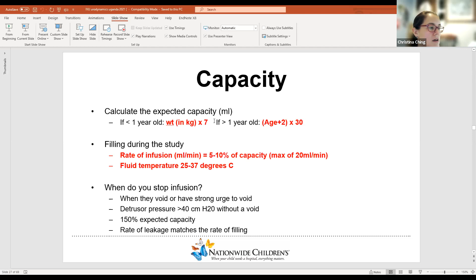You want to make sure the temperature of the fluid is not too cold, to potentially artificially create findings on your urodynamics. You stop infusion when the patient voids or has a strong urge to void, or if you see detrusor pressures going over 40 centimeters of water without a void. If you fill to 150% of their expected capacity, or the rate of leakage matches the rate of filling, you can stop, because basically the study then becomes negligible.